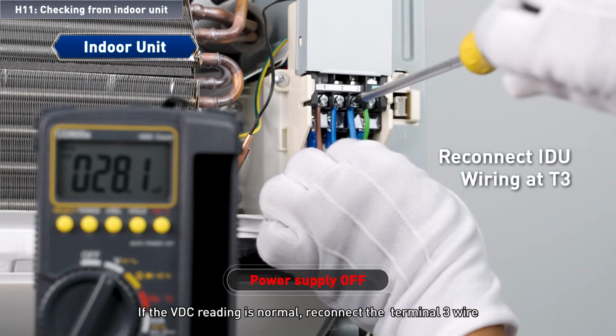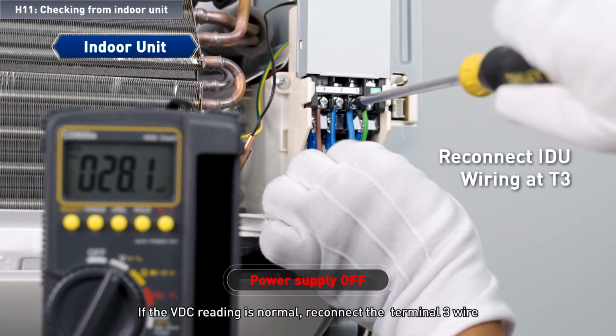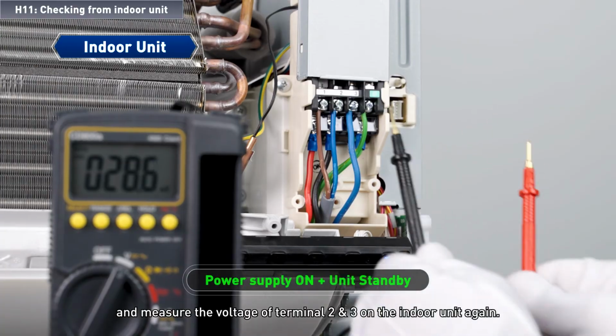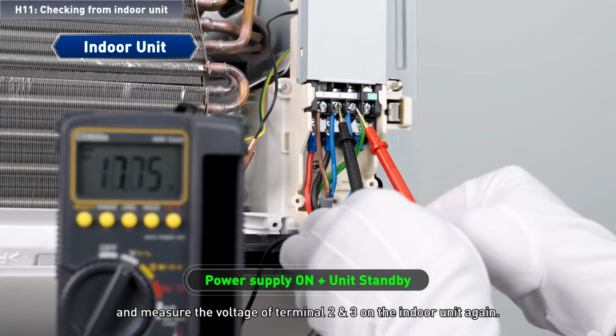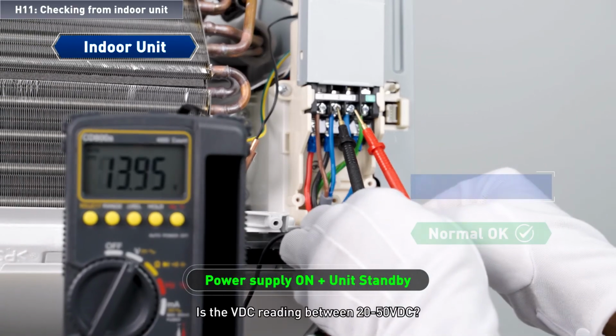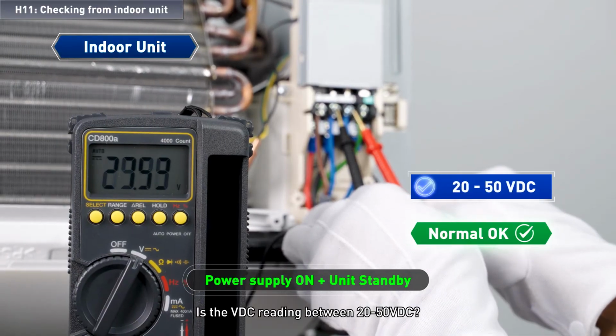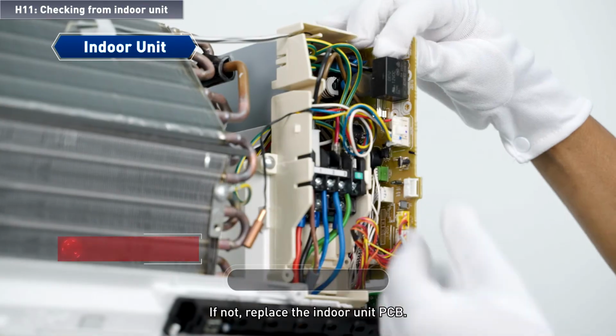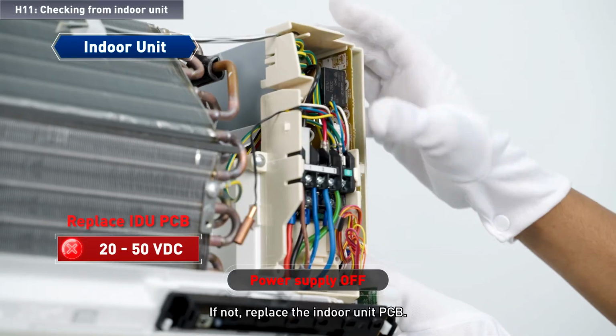If the VDC reading is normal, reconnect the terminal 3 wire and measure the voltage of terminal 2 and 3 on the indoor unit again. Is the VDC reading between 20 to 50 VDC? If not, replace the indoor unit PCB.